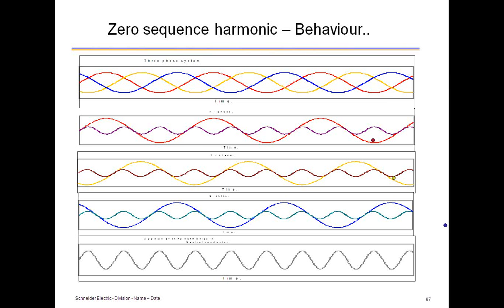I'm just coming to the end of this session. So how exactly do zero sequence harmonics behave in the system? It's critical for building applications where we have a lot of single phase loads, computer loads with SMPS, and so forth. What you're seeing is a 3-phase waveform. We have line 1, line 2, and line 3, and neutral. Between line 1 and line 2 there is a phase angle difference of 120 degrees, and line 2 and line 3 also have a phase angle difference of 120 degrees.